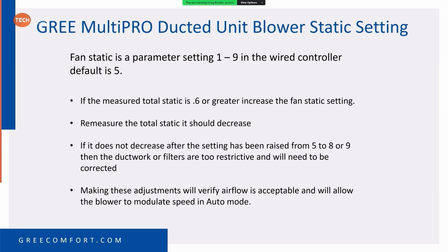You've got ductwork issues. You've got to go figure out whether you got too restrictive of a return or too restrictive of a supply, because if you're cranking that controller all the way up to 9, you're giving that blower more thump. And with that more thump, static should come down. It's almost like if you went in there and put in a bigger blower. You didn't, you just turned up the torque on the blower. And the torque will overcome the static to a point. But if your ductwork is too restrictive, it won't.